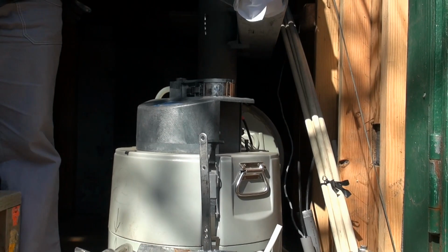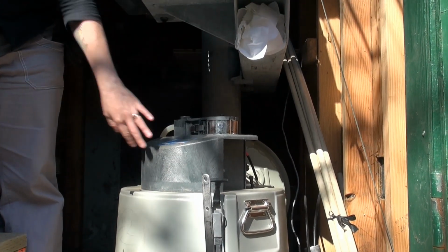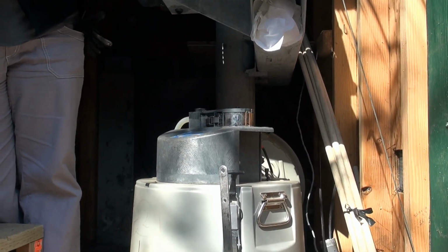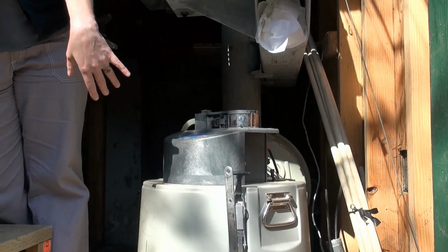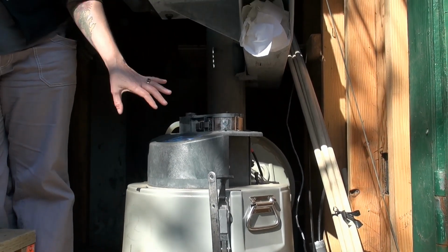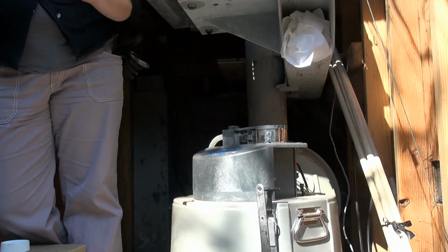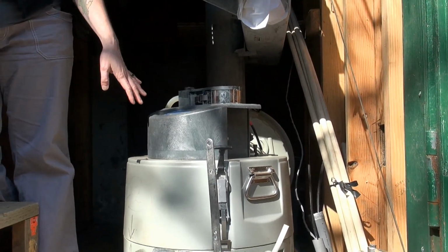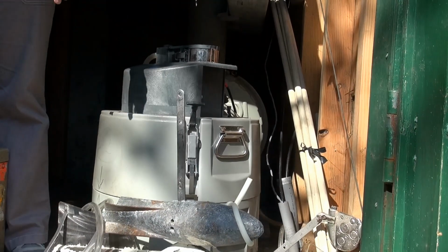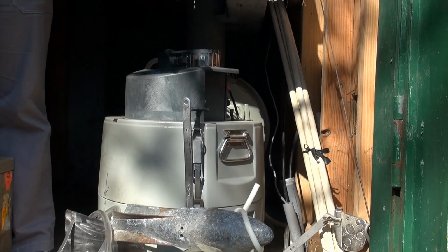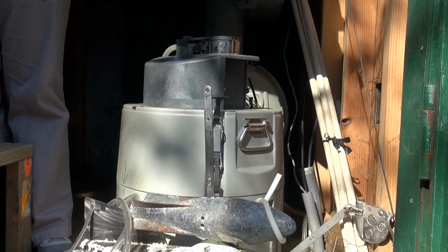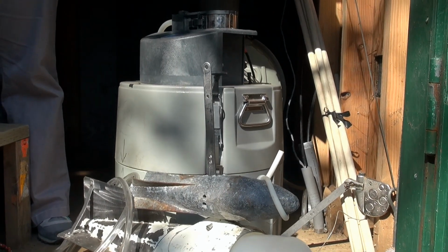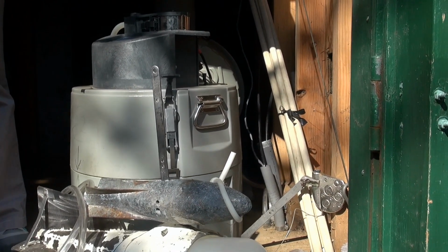Yeah, but it was just a point sample on the edge. What this does is just take a point sample, right here. So then we would have to come out and take the cross-sectional sample, and take point samples in association with it, and do a correction. So if you had pump samples when you didn't have the cross-sectional ones, you could correct these to what the cross-sectional sample concentration would be. Right. Do you find much difference?